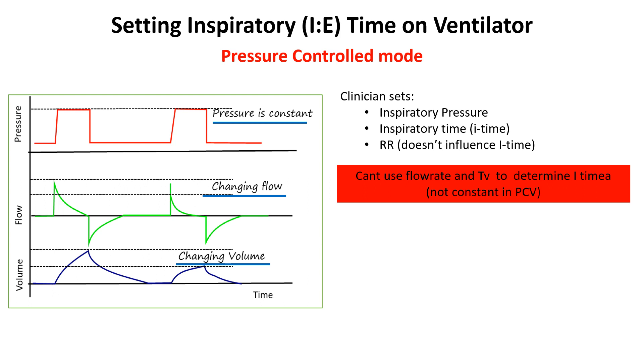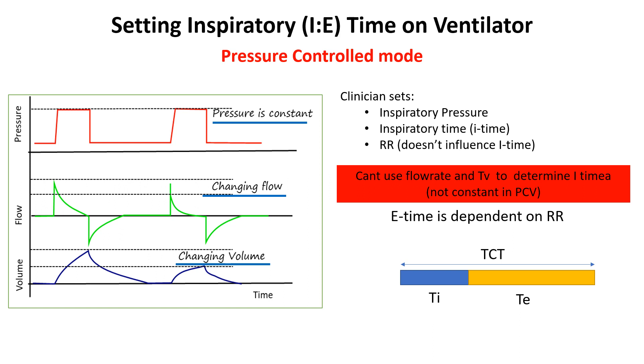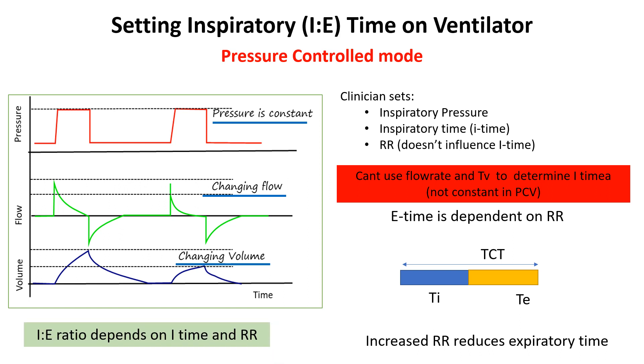The respiratory rate is also set, but it doesn't directly control the inspiratory time, as that is set by the clinician. The expiratory time, however, is completely dependent on respiratory rate. Respiratory rate determines the total cycle time and thus influences the expiratory time. If the total cycle time is short, expiratory time also reduces, since inspiratory time is fixed by the clinician. Thus, the IE ratio in pressure control ventilation is determined by inspiratory time and respiratory rate.